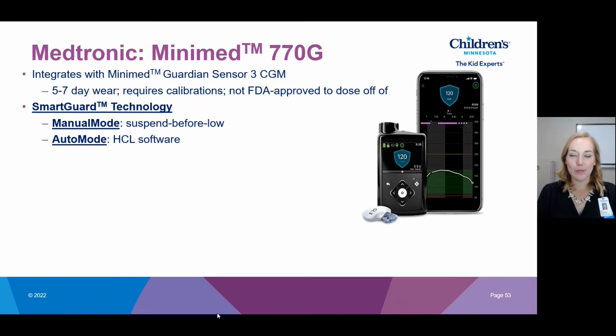Auto mode is the hybrid closed loop software system that's available on the 770G. It is available for ages 2+, and you must be using a minimum of 8 units of a total daily dose. So what this means is both of your basal insulin and all of your boluses added up for the entire day must equal 8 units. This is just to help the algorithm in that hybrid closed loop therapy work its best.